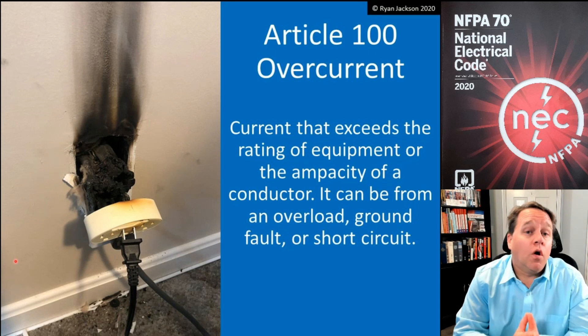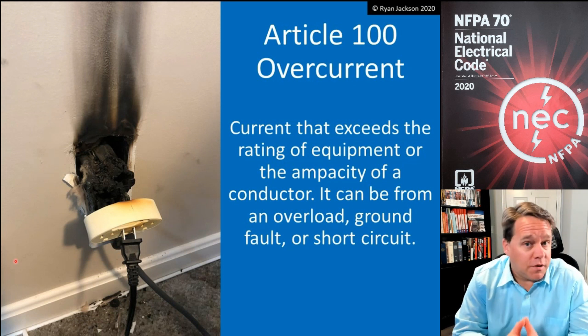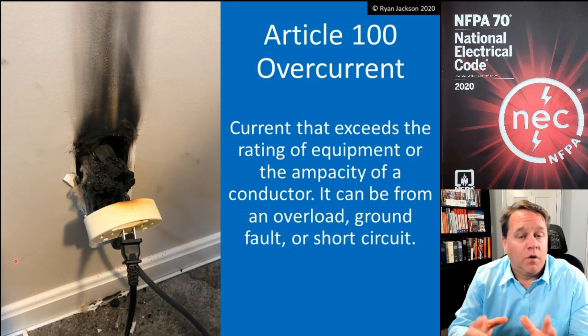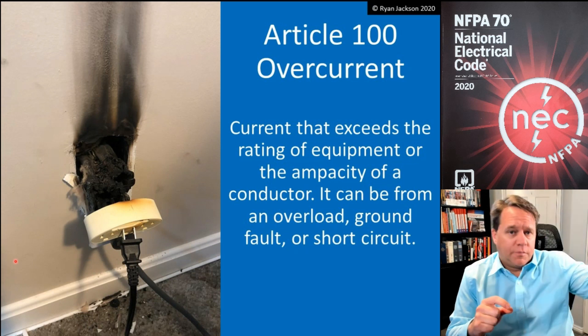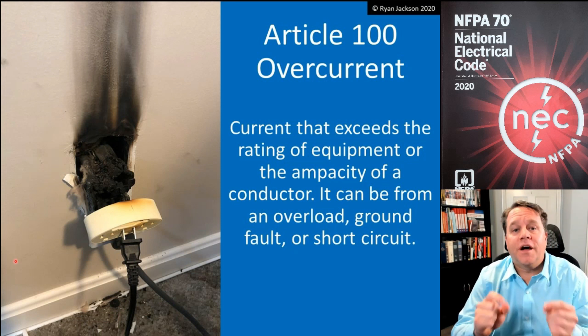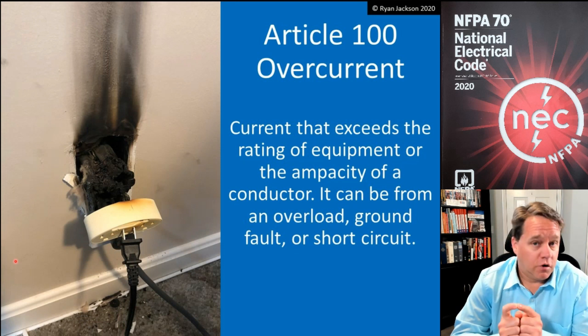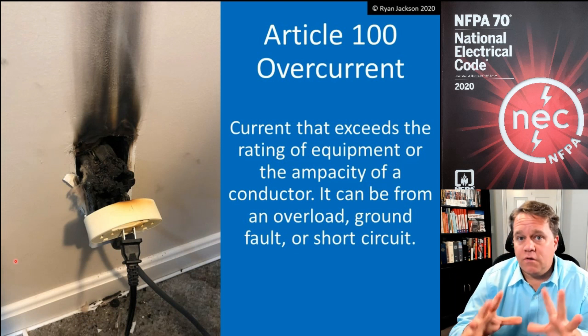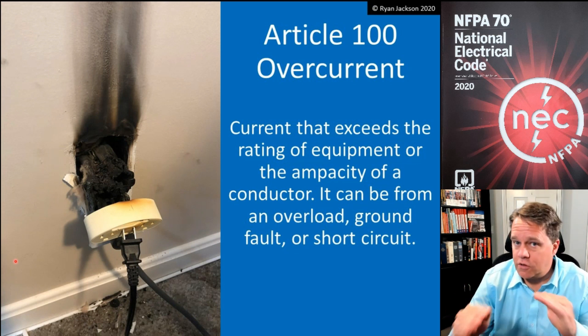Article 240 protects conductors from overcurrent — that's all Article 240 does. It does not protect equipment. If you want to protect equipment from overcurrent, you have to go to the equipment article. For example, if supplying a transformer, go to Article 240 to protect the conductors feeding and leaving the transformer, but for the transformer itself go to Article 450. The same applies to panelboards, receptacles, or anything else.